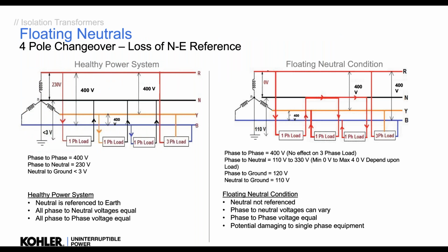Okay, so what we're worried about is not this one on the left. This is a healthy one, and the neutral is connected all the way through to the earth. Okay, so line to neutral is 230, line to line 400. Okay, neutral earth 0. On the right, we have a distributed neutral floating. This is where the neutral is broken with reference to the supply transformer, a distributed neutral. Okay, this is obviously a dangerous situation, and so the voltage between line and neutral could rise to anything. Line to line will remain 400, but the problem here is that it is dangerous. Okay, and this is one type of floating neutral, but it's not the floating neutral that we're trying to overcome.